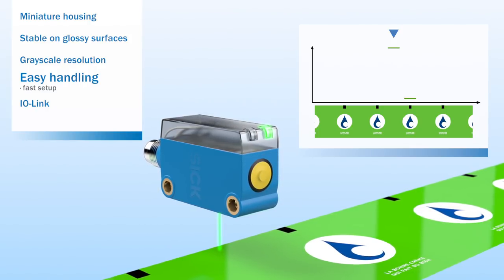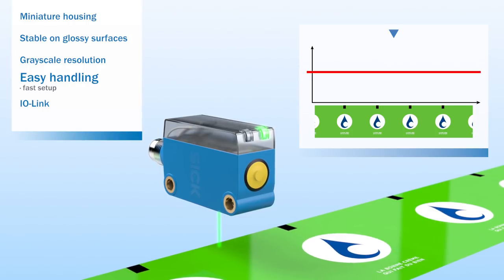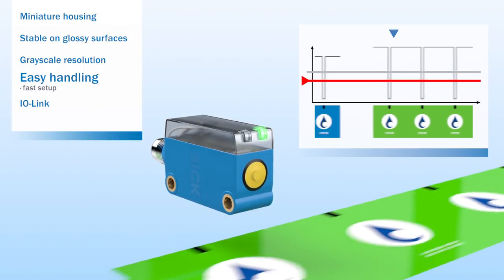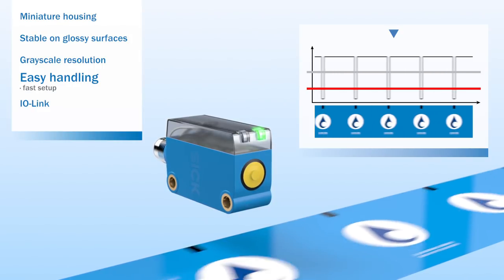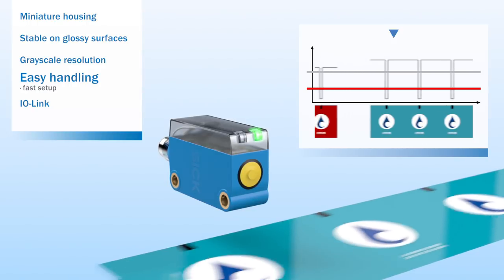The optimum switching threshold is determined so work can continue. For special applications, a close-to-mark teach-in method can be used for optimum handling where backgrounds change but the mark remains consistent.